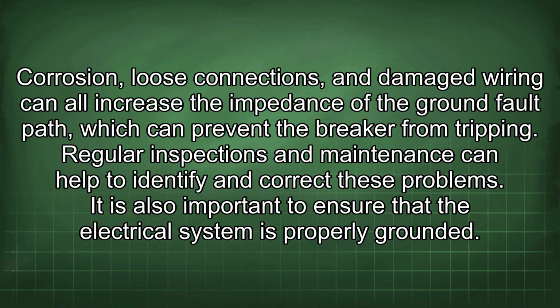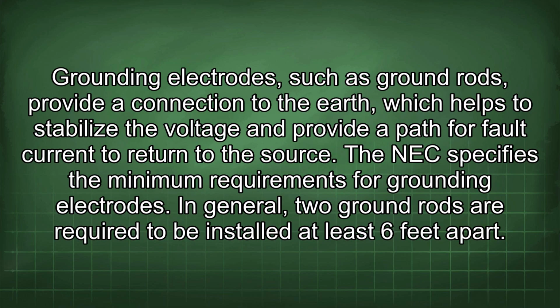Corrosion, loose connections, and damaged wiring can all increase the impedance of the ground fault path, which can prevent the breaker from tripping. Regular inspections and maintenance can help to identify and correct these problems. It is also important to ensure that the electrical system is properly grounded. Grounding electrodes, such as ground rods, provide a connection to the earth, which helps to stabilize the voltage and provide a path for fault current to return to the source.